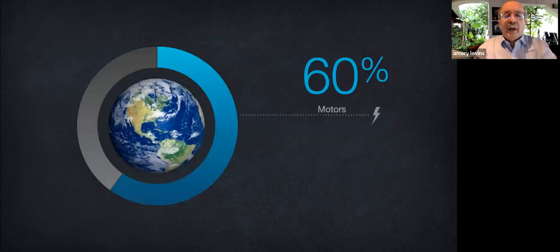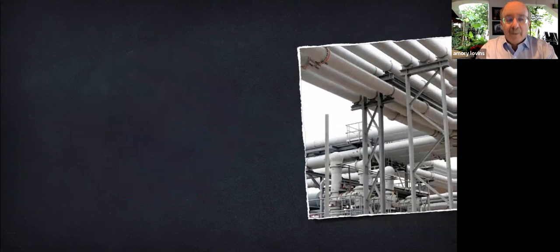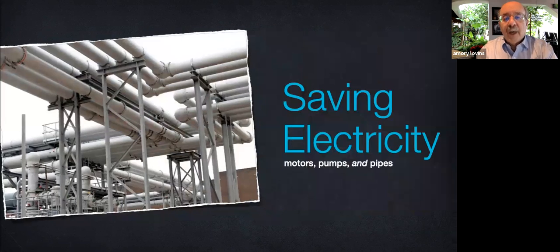At least half, more likely 3/5 of the world's electricity runs motors. Half the world's motor torque runs pumps and fans, mostly pumps. Pumps move liquid through pipes. IPCC in 2014 said that 43 to 57% of pumping energy in about 32 countries could be saved in principle, and 27 to 49% could be saved cost effectively.